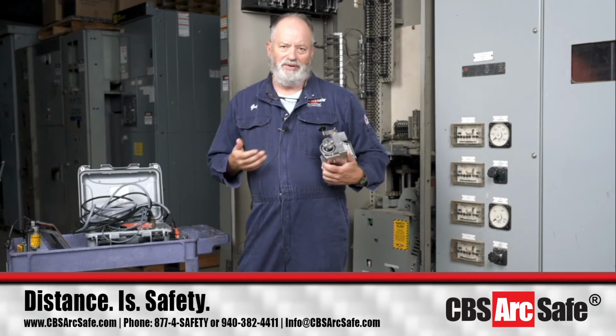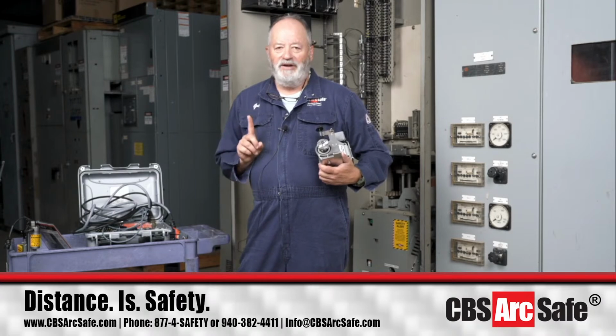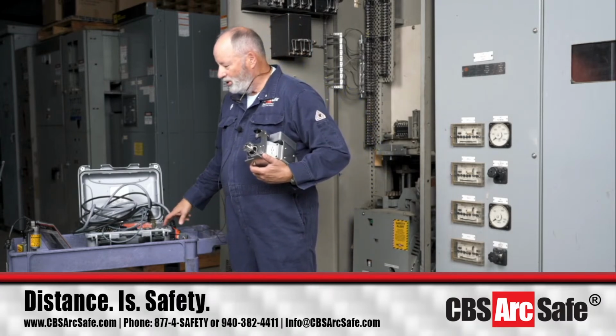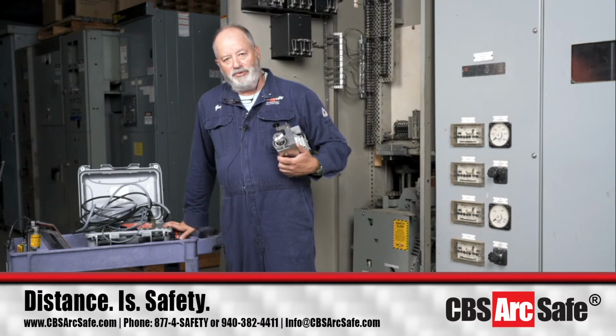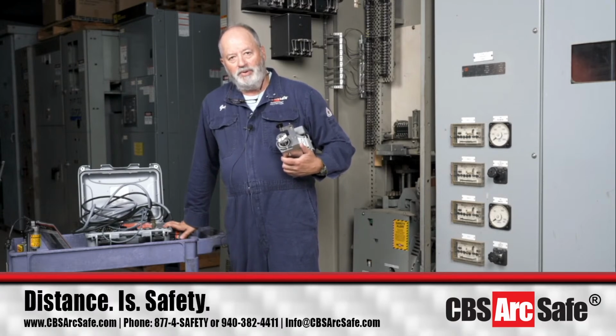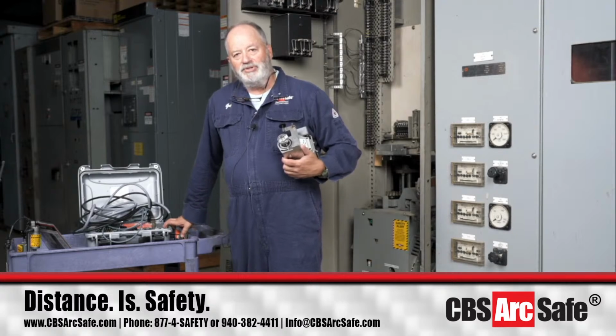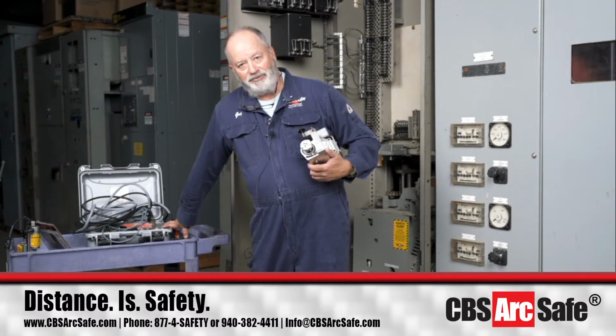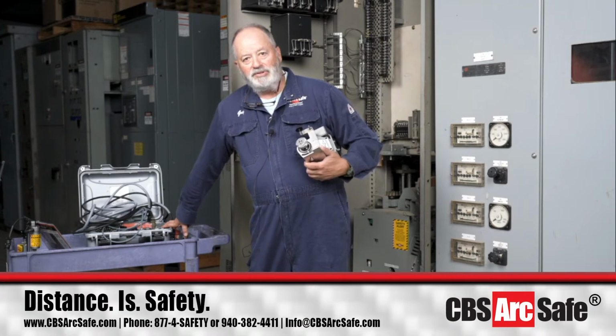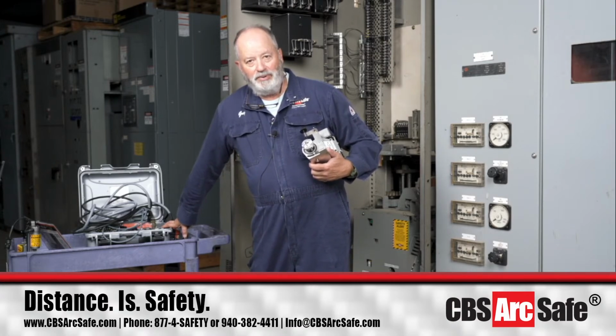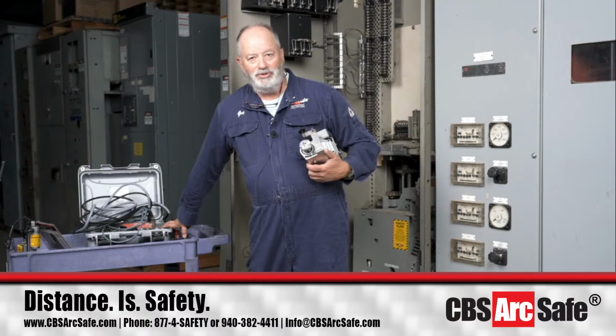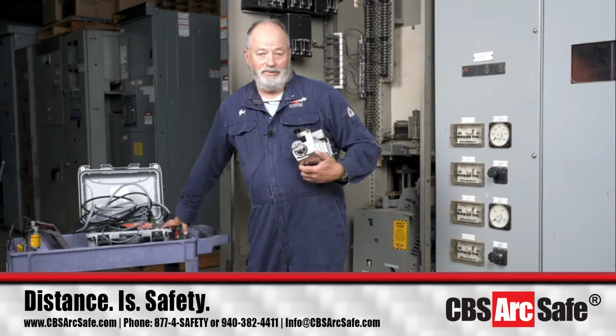Okay, Greg, your motor's wound for 120 AC. We've solved that problem because the supervisory link, which would normally go directly from the motor to the cubicle, isn't associated that way. Instead it goes to the control box here for the RS3 MB2, and it interprets whatever power the cubicle has so it can figure that out for itself. The motor is powered based on the control input you give it, for either racking the breaker in or out, up or down.